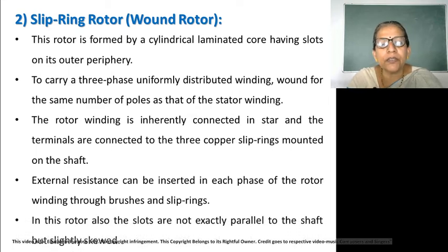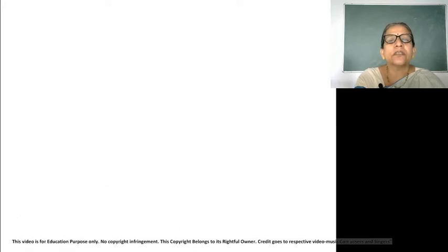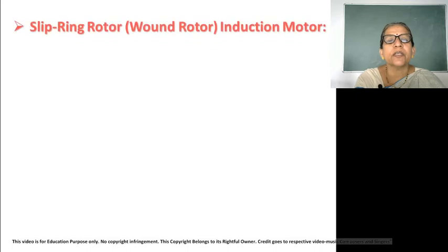In this rotor also, the slots are not exactly parallel to the shaft but slightly skewed. The purpose, as I already explained, is that it avoids the interlocking of the stator and rotor poles, and it avoids the humming sound which is produced due to interlocking.